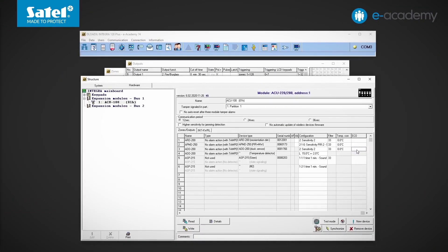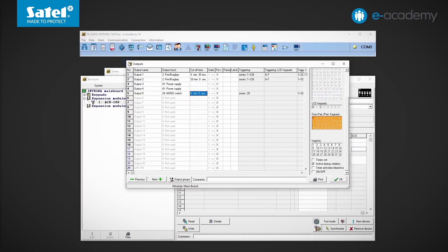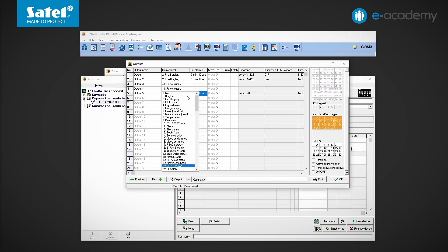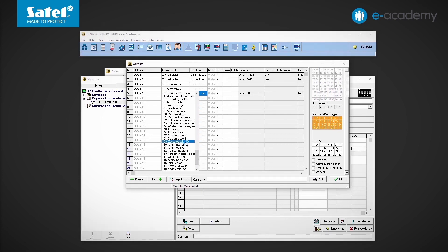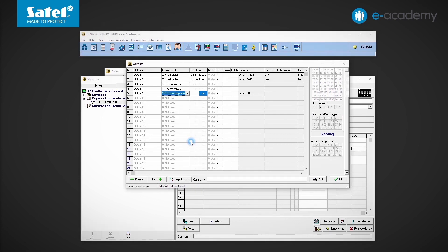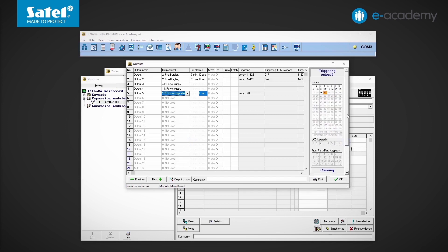We are returning to the DLOADX program. To control the output with a temperature detector, we can use an output type other than mono switch. This can be type number 109, zones logical AND. If only one triggering zone is indicated at output type 109, then this output will be active only when the marked zone is violated.